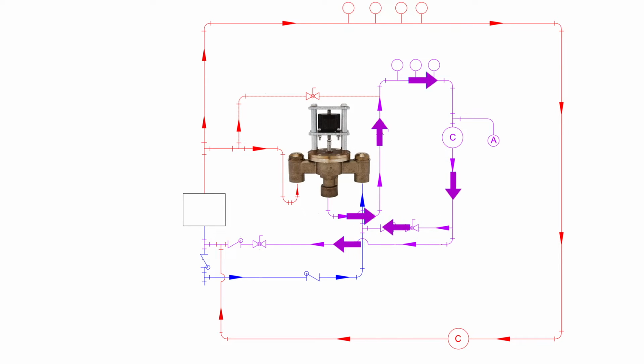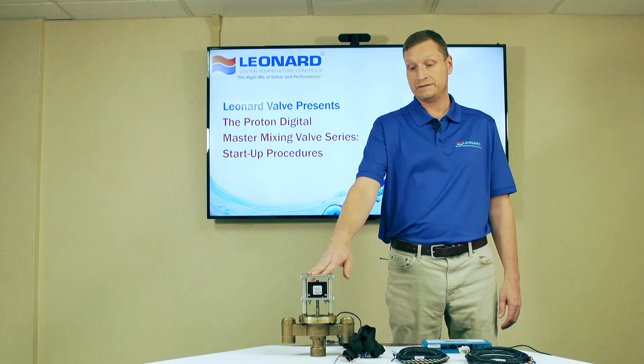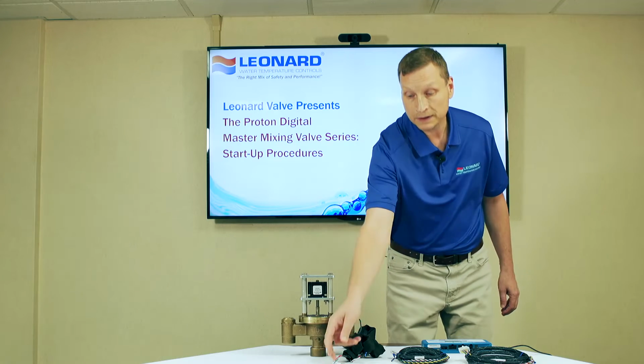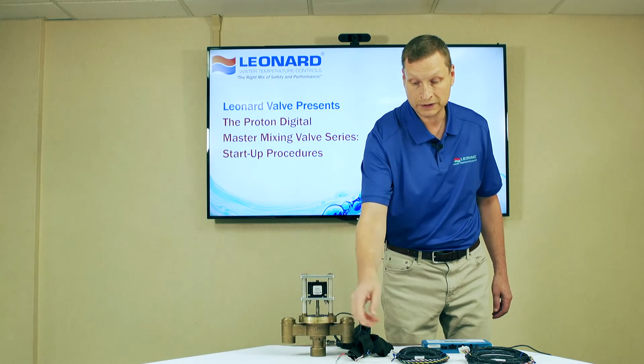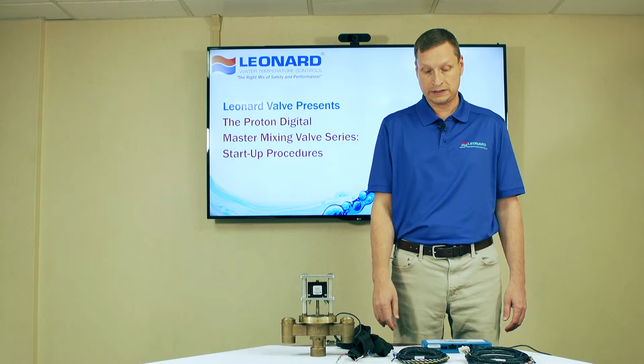The key to the setup and proper function of the valve is going to be the piping. Please follow the piping diagram as shown on the screen with all the check valves and ball valves required. From there, once the valve is installed, you're going to be able to wire up the motor connector, 4-pin motor connector, and the 3-wire RTD.